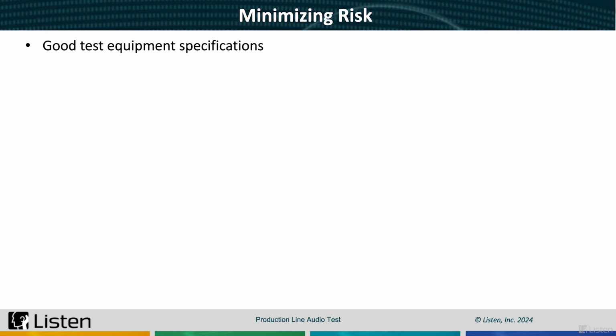There is a big difference between requiring frequency response within 3 dB of golden unit and specifying frequency response within 3 dB of the golden unit, measured at the start of each batch in a well-controlled test environment using SoundCheck version 22 and Audio Connect 2 running this provided test sequence.